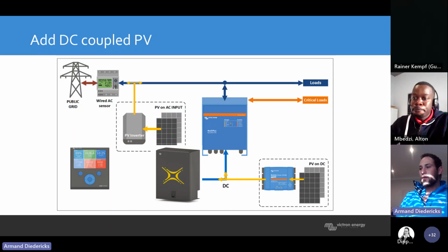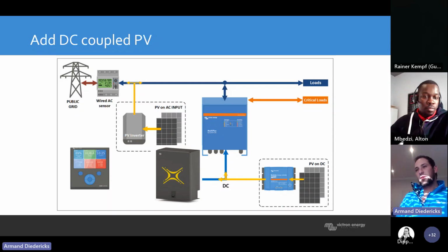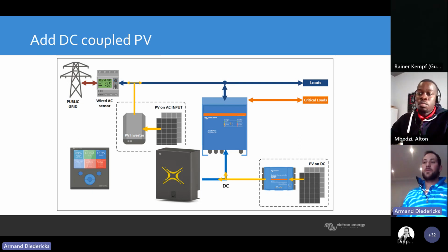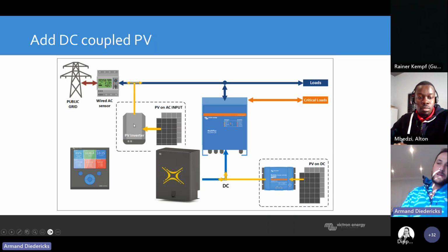Exactly. And a big thing most clients do is that the system doesn't communicate, and it keeps on dropping info or communication. Once it drops communication on the Fronius, if your Cerbo or your GX device doesn't pick up the IP address from your Fronius, it will drop it, and the Fronius will stop producing. So what they do is they connect the grid tie inverter to the Wi-Fi. And the Wi-Fi sometimes does have a delay. If there are communication interface problems, you will have a delay on production. Your grid tie inverter will switch off and on and off and on.